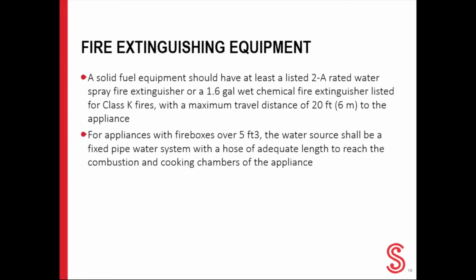Now that you have safely ignited your fire, let's talk about extinguishing equipment. All solid fuel appliances that produce grease vapors and have fireboxes of less than 5 cubic feet need to have a minimum of a 1.6 gallon Class K or a 2A water spray rated fire extinguisher within 20 feet of the solid fuel appliance. The solid fuel appliance needs to have its own fire extinguisher. Therefore, if you have another cook line, you will have to have at least 2, one for the cook line and then one for the solid fuel.